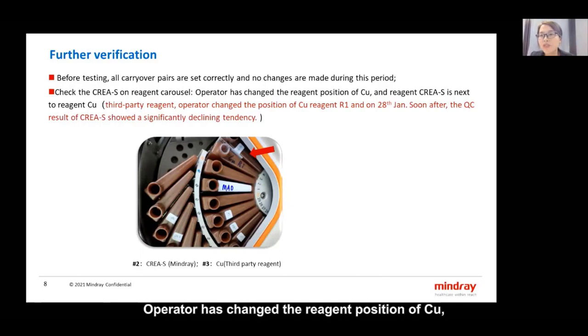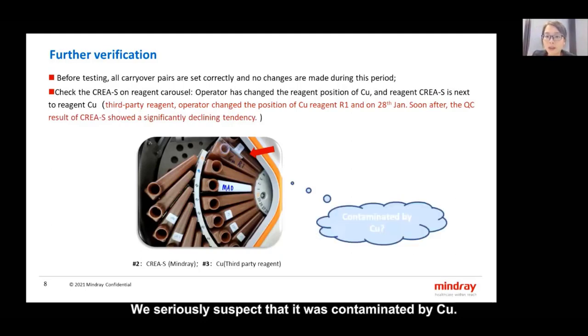The operator had changed the reagent position of Cu, and the creatinine reagent is next to reagent Cu. Reagent Cu is a third-party reagent. The operator changed the position of Cu reagent 1 on 28 January. Before this time, the creatinine reagent and reagent Cu were far apart. Soon after, the QC result of creatinine showed a significant declining tendency. We seriously suspected it was contaminated by Cu.